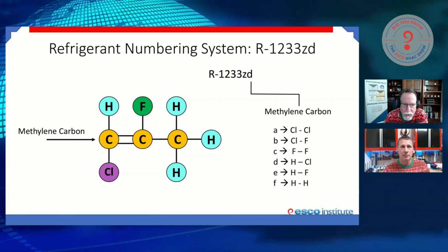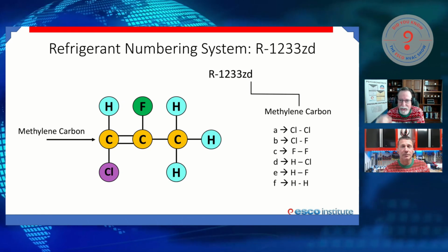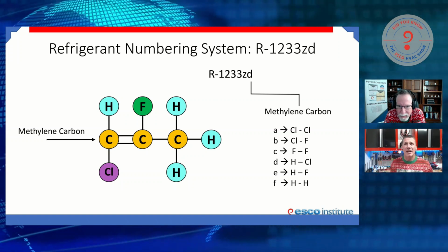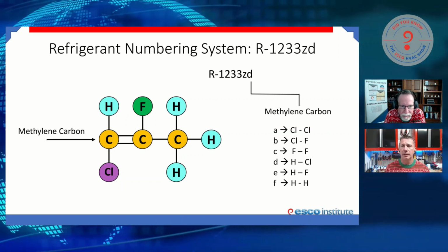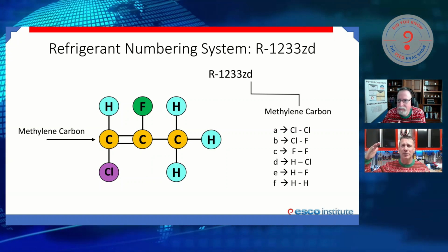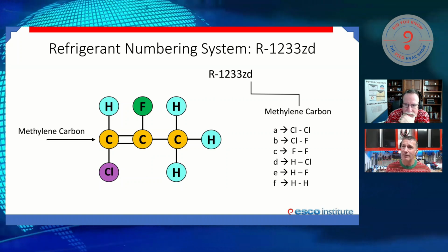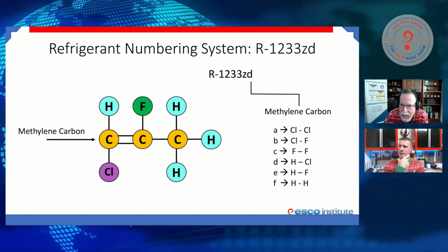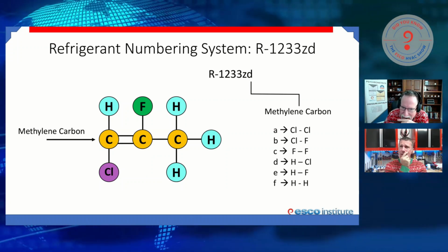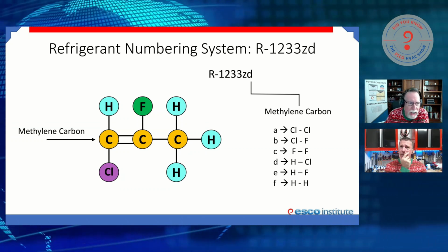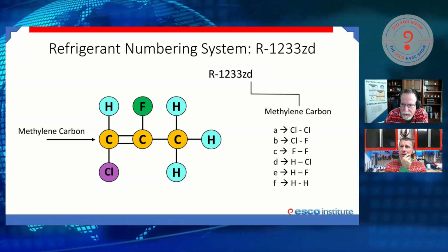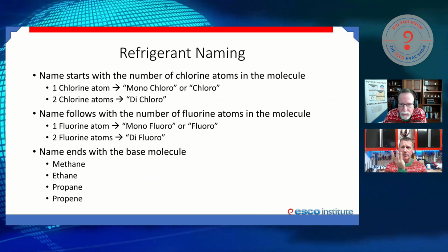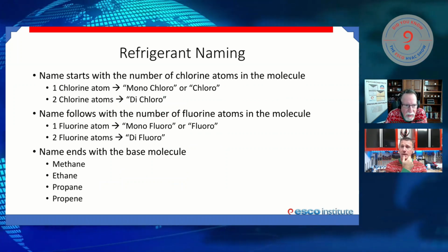So 1233zd looks like that. 1233zd, which is an HFO refrigerant, actually contains chlorine. I thought I was crazy when I was reading the chemical attributes, because I always go on Wikipedia and look through the different chemicals when I see something I'm not familiar with, because it breaks out the chemical components. Yeah, this annoys a lot of people: how can it have chlorine? That's exactly what I said. Remember, 1233zd is an unsaturated molecule, so it doesn't last long enough in the atmosphere to do any damage to ozone. The chlorine breaks apart easier, comes back down to the ground, and is not a suspended particle in the atmosphere.